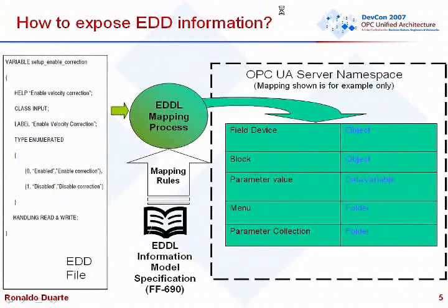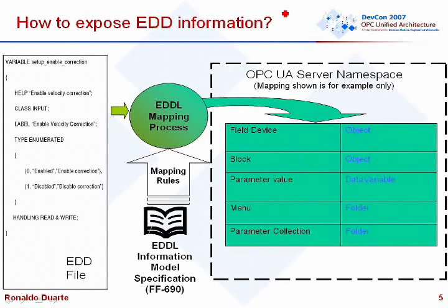After locating the EDD on the hard disk of the computer, we perform the mapping process defined by the EDD information model that Nestor described. This specification defines mappings between what needs to be extracted from the EDD and what information goes into the OPC UA nodes. For instance, the information model says: whenever you find a field device, create an object, instantiate it, and fill its attributes with information from the EDD.